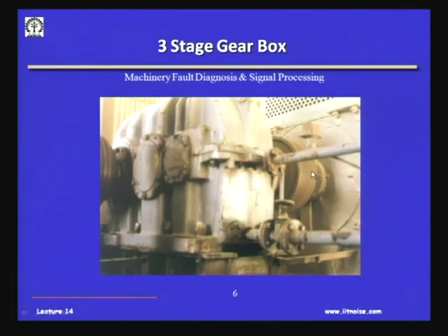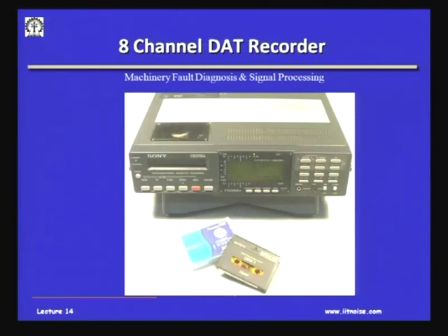And because of, I would say, defects, because of obvious reason there are certain defects. So, we put accelerometer at the bearing locations, accelerometer near the foundations, and we had taken the measurements of this vibrations simultaneously. And obviously, this analysis, as I was telling you, Cepstrum cannot be done real time on the fly. So, we have to record the signals in a DAT recorder, wherein you can record almost 8 channels of vibration simultaneously to a bandwidth of 20 kilohertz.